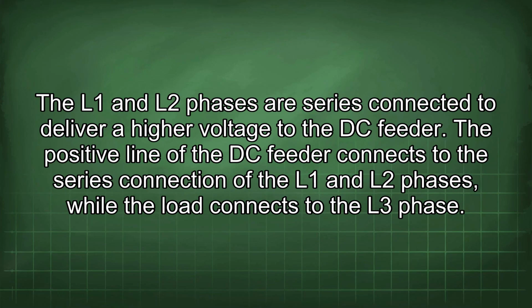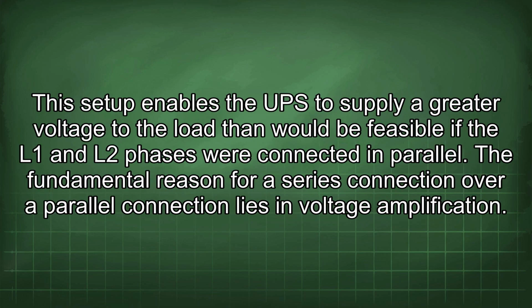The L1 and L2 phases are series connected to deliver higher voltage to the DC feeder. The positive line of the DC feeder connects to the series connection of the L1 and L2 phases, while the load connects to the L3 phase. This setup enables the UPS to supply a greater voltage to the load than would be feasible if the L1 and L2 phases were connected in parallel.